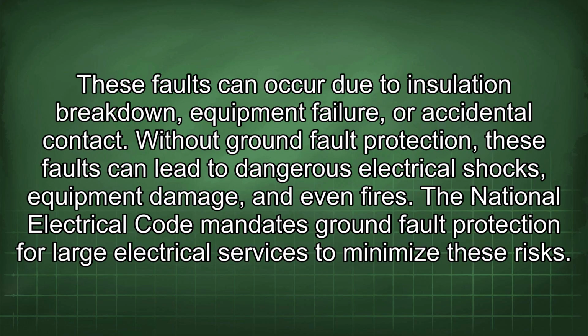These faults can occur due to insulation breakdown, equipment failure, or accidental contact. Without ground fault protection, these faults can lead to dangerous electrical shocks, equipment damage, and even fires. The National Electrical Code mandates ground fault protection for large electrical services to minimize these risks.